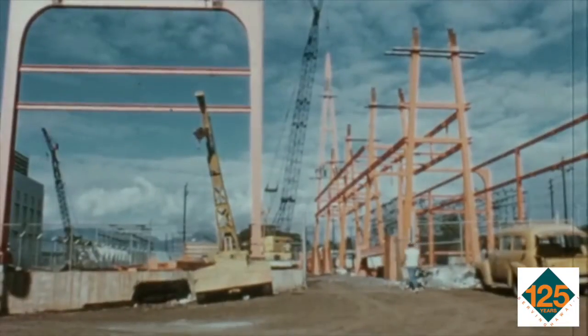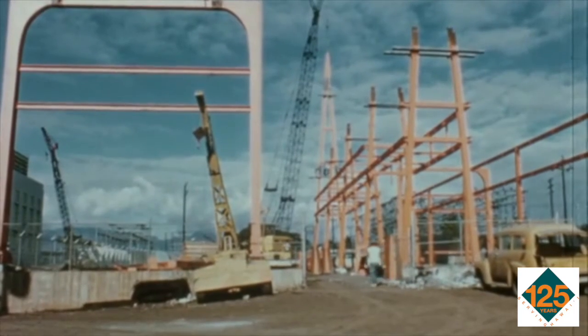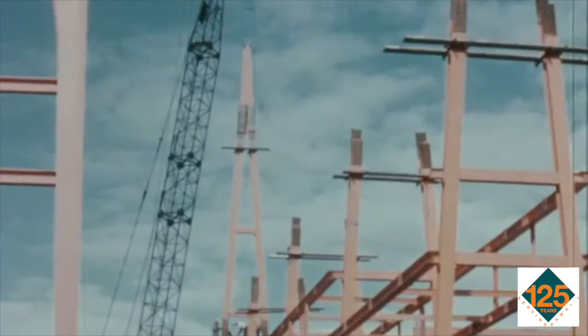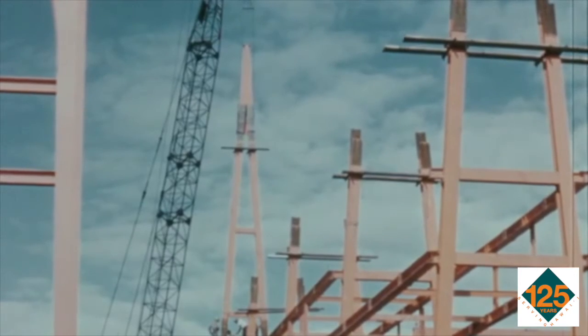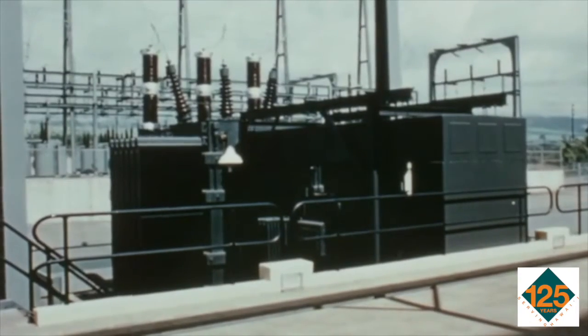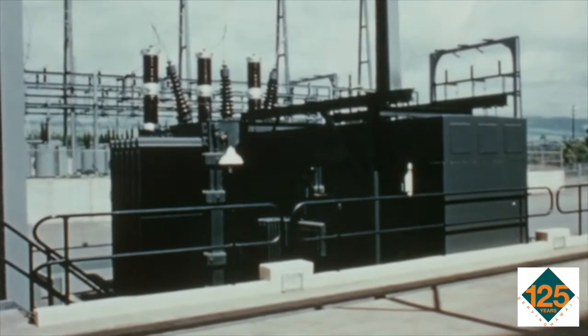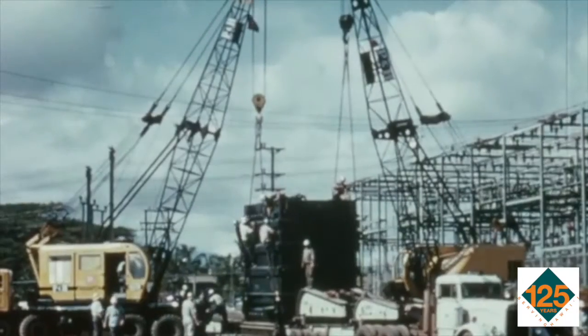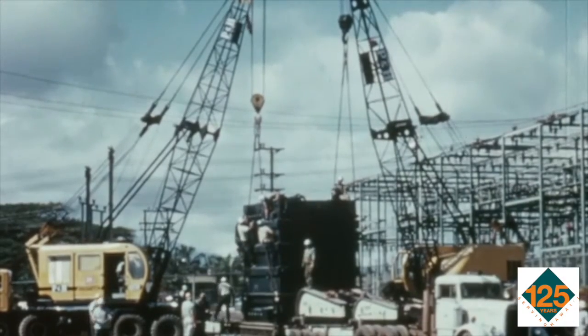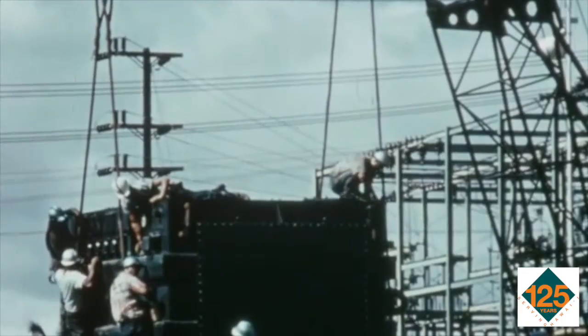While the power plant was under construction, Hawaiian Electric was building a 138,000 volt transmission system, the highest voltage ever used in Hawaii. Electric power has its ups and downs. It comes out of the generator at 12,000 volts. This transformer boosts it to 138,000 volts. Then the substations take it down again to lower voltages for distribution to customers.